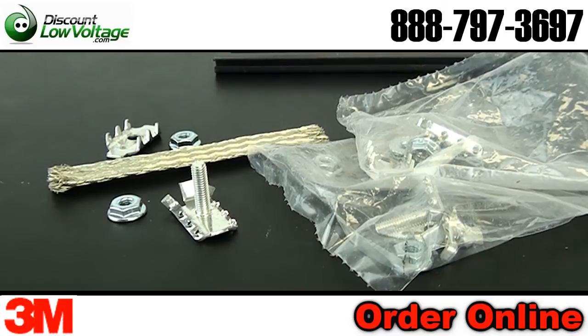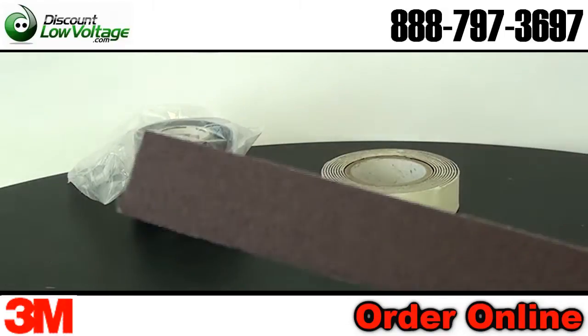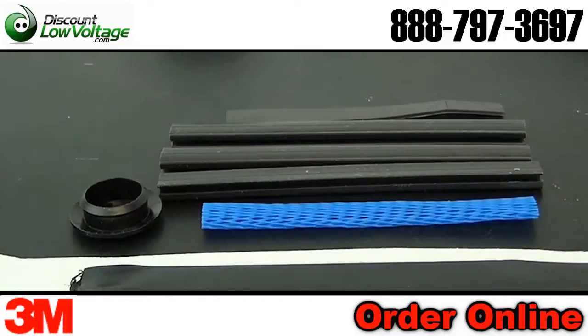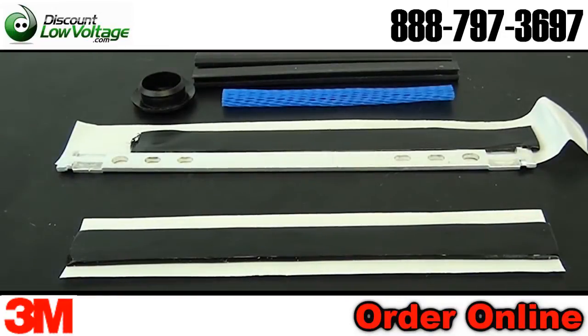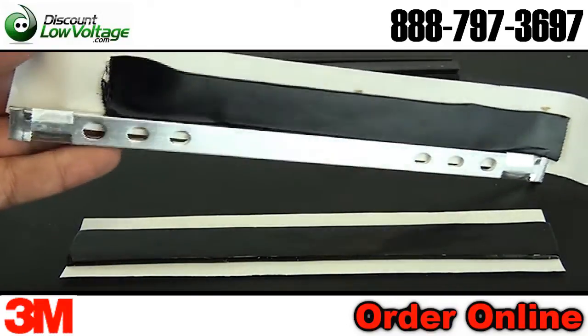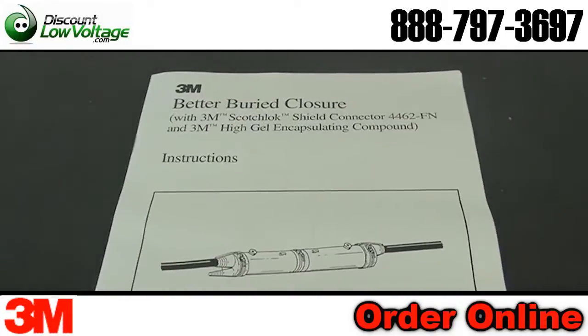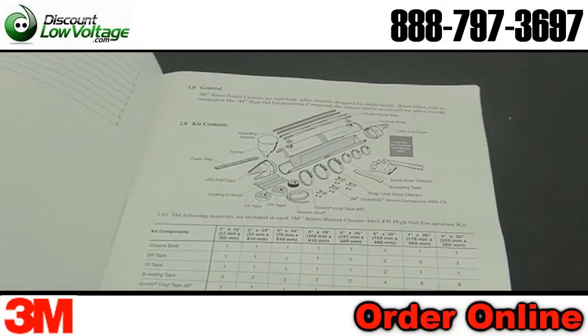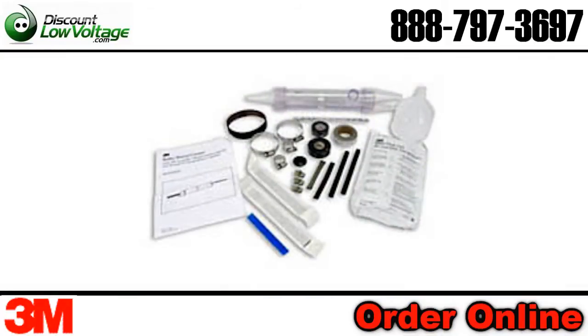Tapered end caps can be terminated and slit for exact cable size requirements. Strain relief bars can be installed on a single or double sheath cable to protect the splice from electrical interference and damage from cable tension. The spacer web is designed to protect splice connectors by positioning them away from the closure walls. Hose clamps secure the closure body and end caps.